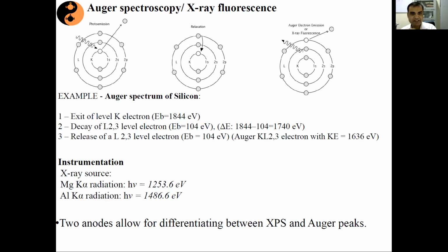To really identify that, we need two X-ray sources in our chamber, so that we have two incident photon energies.